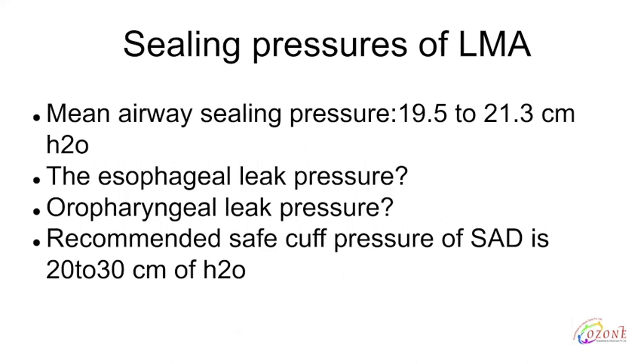The esophageal leak pressure is defined as the pressure which breaks the seal between the cuff of supraglottic airway devices and pericuff mucosa, allowing penetration of fluid into the pharynx and oral cavity. Cuff overinflation and external pressure on the neck can impair the sealing capability of the LMA during a sudden increase in esophageal pressure.